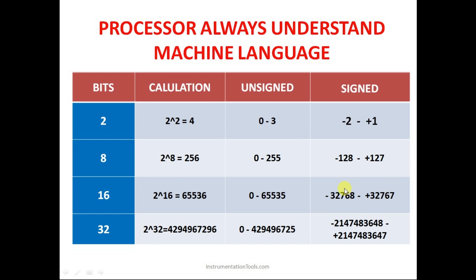The CPU then converts this digital value into the physical quantity and displays it on the computer screen. In the case of Siemens, the maximum positive range used is 0 to 27648. So for 4mA (minimum) the digital value is 0, and for 20mA (maximum) the digital value is 27648. In our example: 4 to 20mA of current maps to 15 to 85 inches of level, and 0 to 27648 is the corresponding digital value.